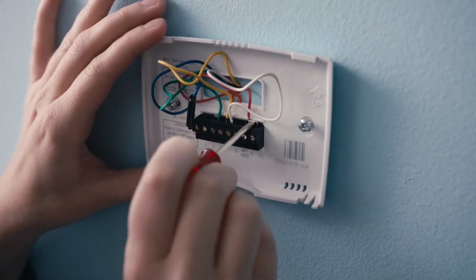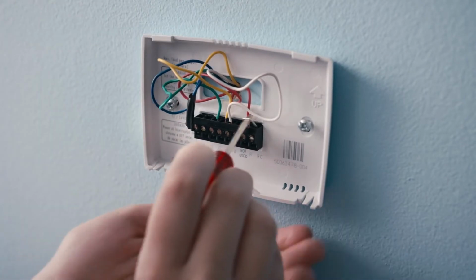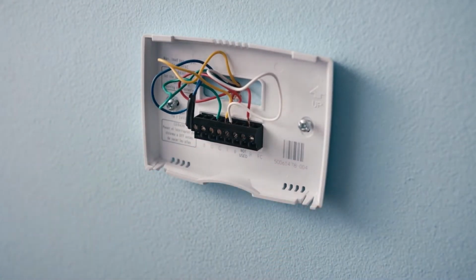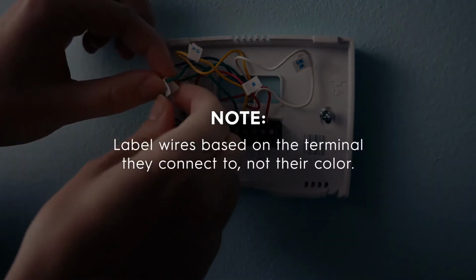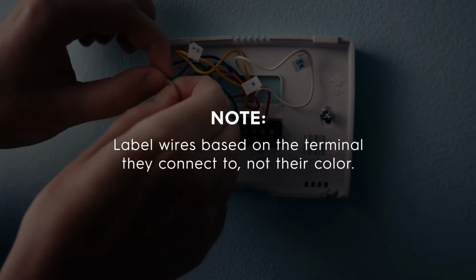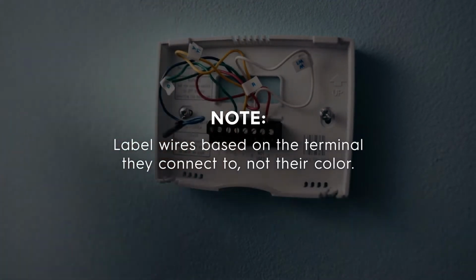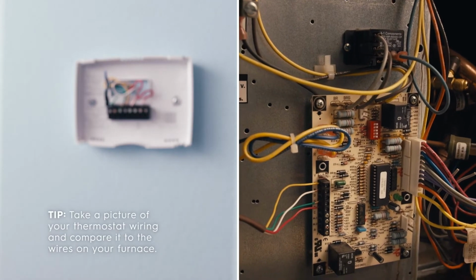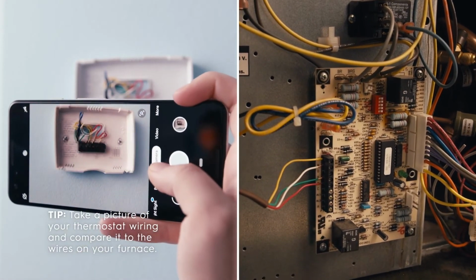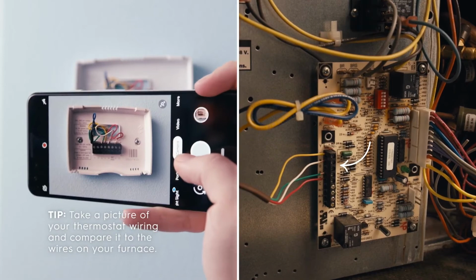Next, you'll remove any jumper wires connecting the 2 terminals, like RH to RC. Using the labels provided, label your wires based on the terminal they connect to, not on their color. To make sure you're labeling the wires correctly, it helps to take a picture of your thermostat wiring and compare it to the wires on your furnace.